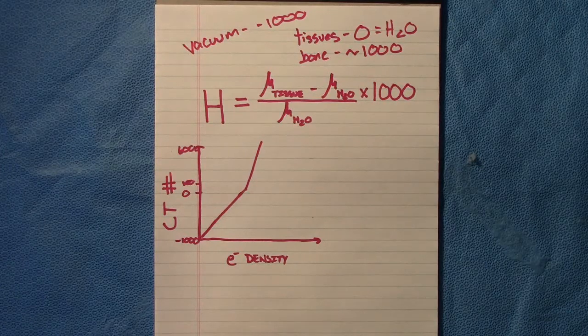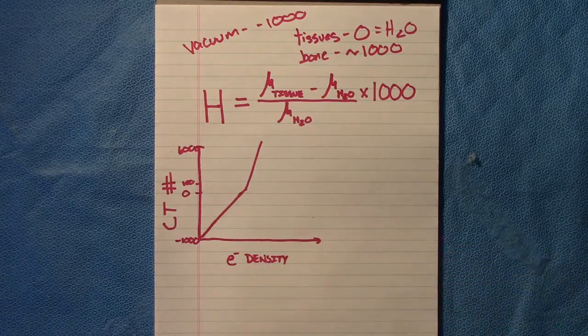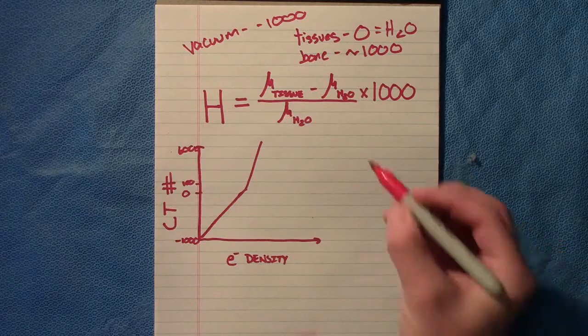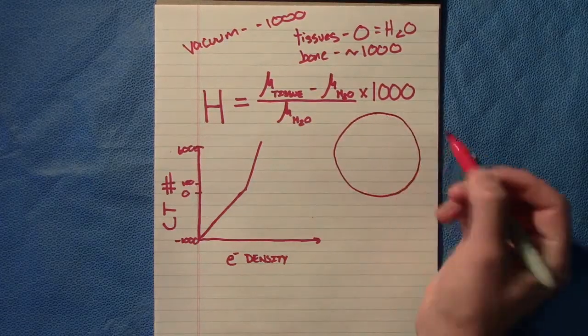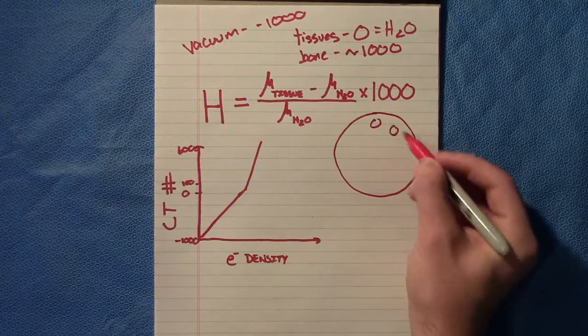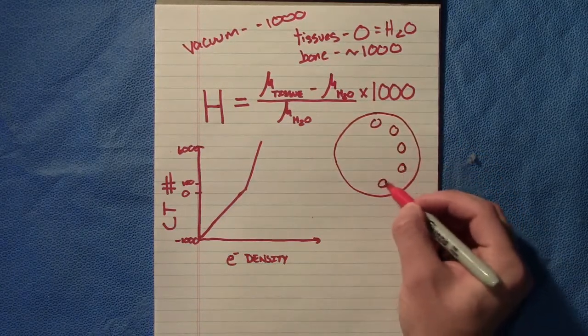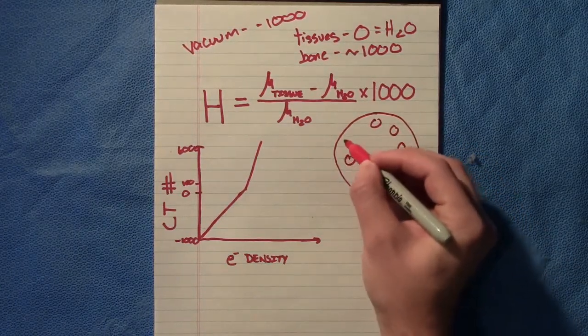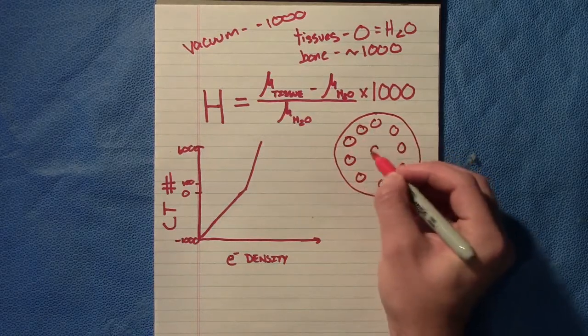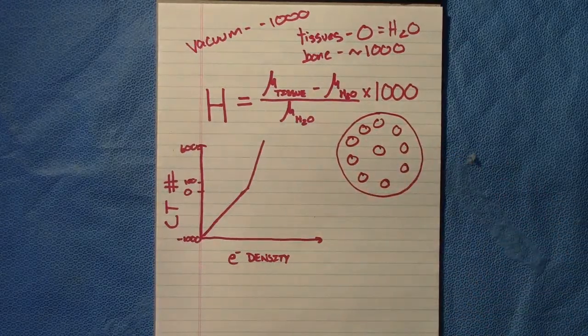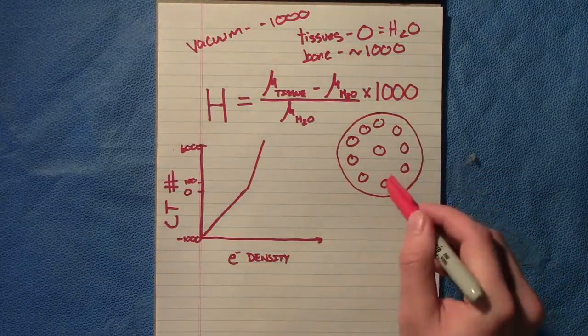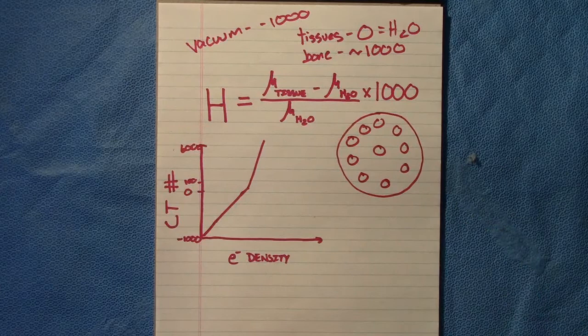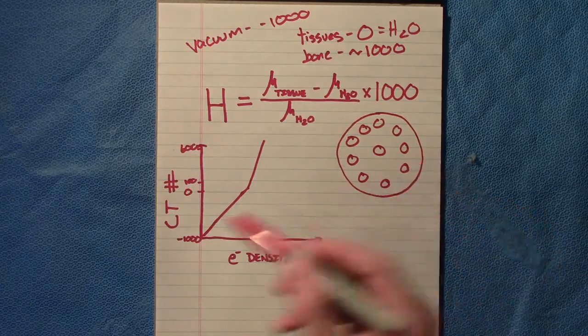At this point we've scanned a phantom, and that Gammex phantom is just a circular phantom like this, and it has a bunch of plugs in it. All these plugs—PMMA, acrylic, water, bone—there's just all types of different plugs and materials that they know the electron density of.